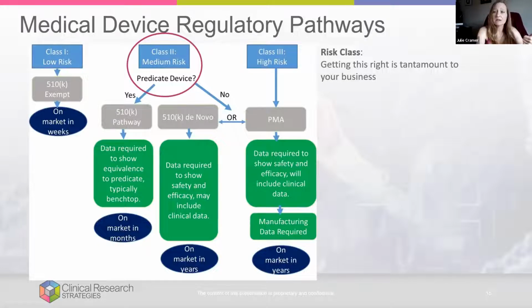If you have a predicate device and it's noted as substantially equivalent, then you can go the 510K pathway. The only data that you need is to show equivalence to the predicate. Typically, that's just benchtop saying I'm equivalent to the predicate for these reasons. The FDA says, okay, you're on the market in months. If you don't have a predicate device, like we said before, you can go to the 510K de novo pathway. So you have to show data that's safe and effective, but oftentimes the bar isn't quite as high because you're only a medium risk. On the market in years.